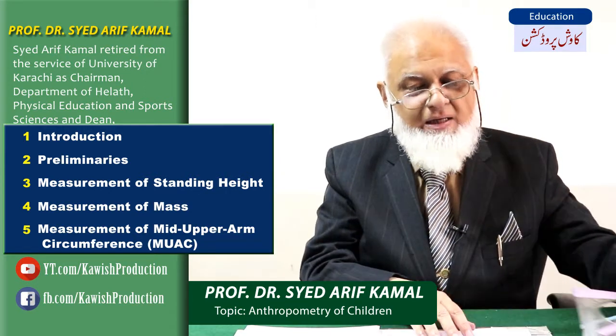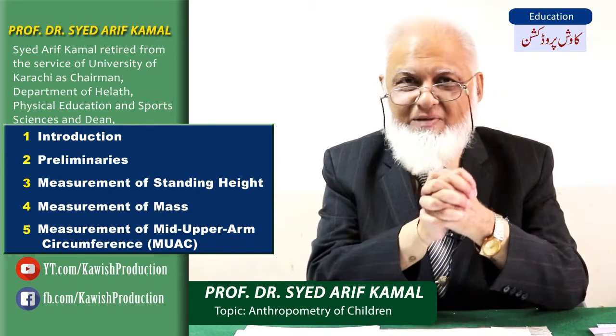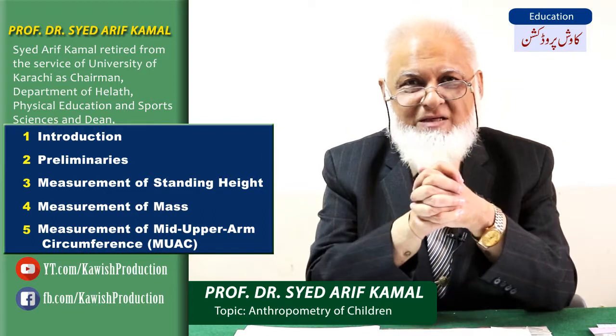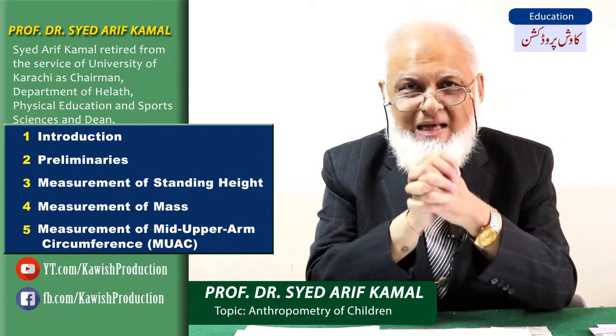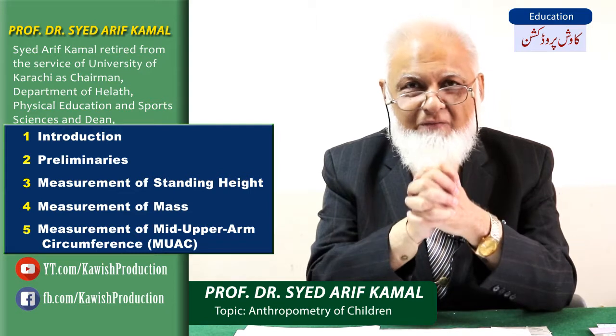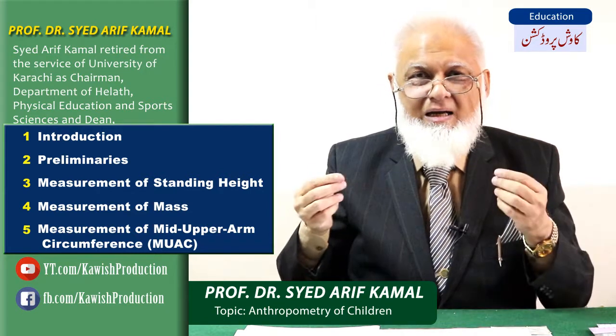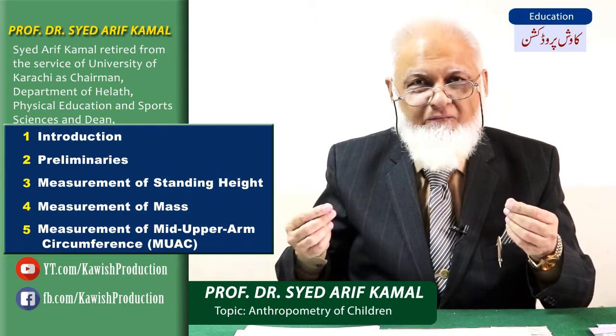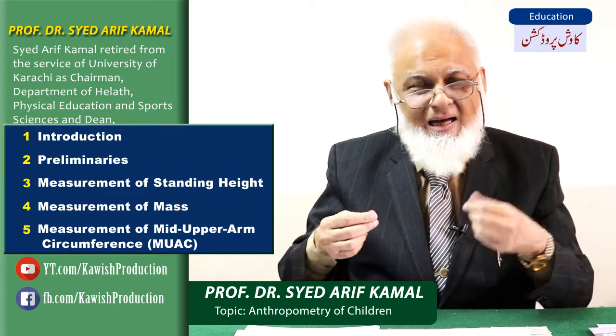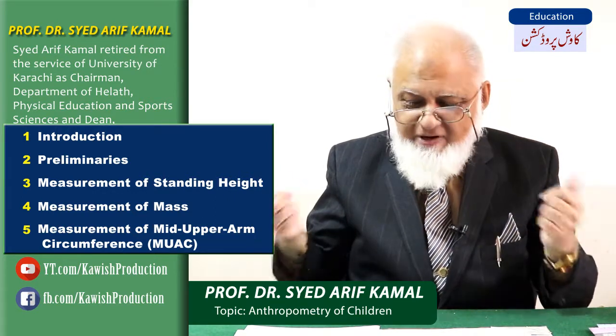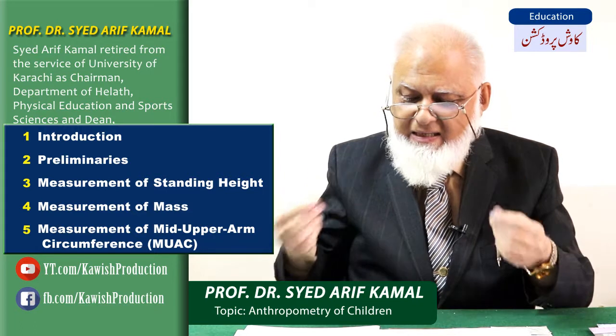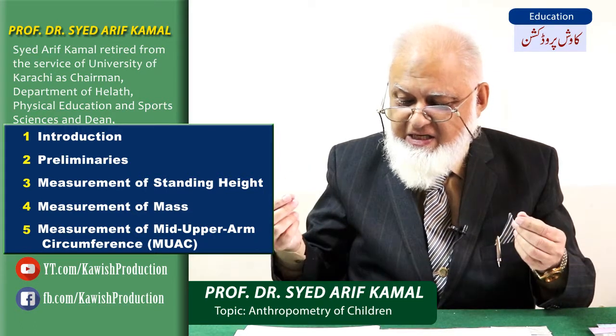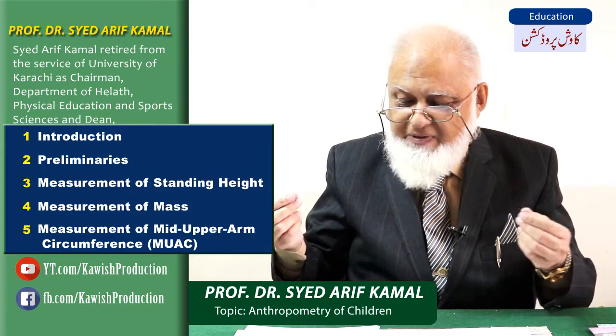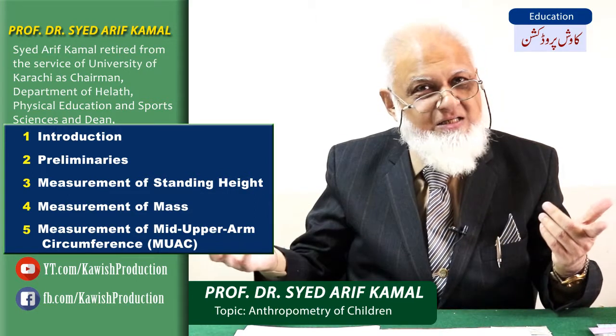Whenever you are doing any scientific or laboratory measurements, you have to check whether the equipment is performing properly at the start of each session, let's say every day. So at the start of each daily measurement session, a standard cylinder must be used to check if the mounted scale is working properly.